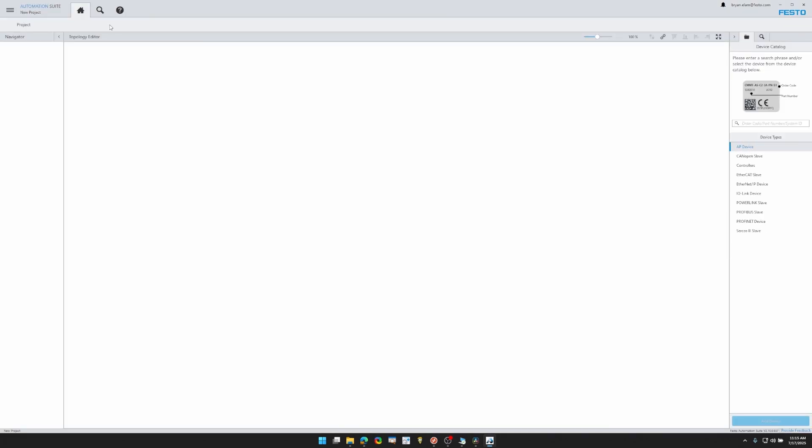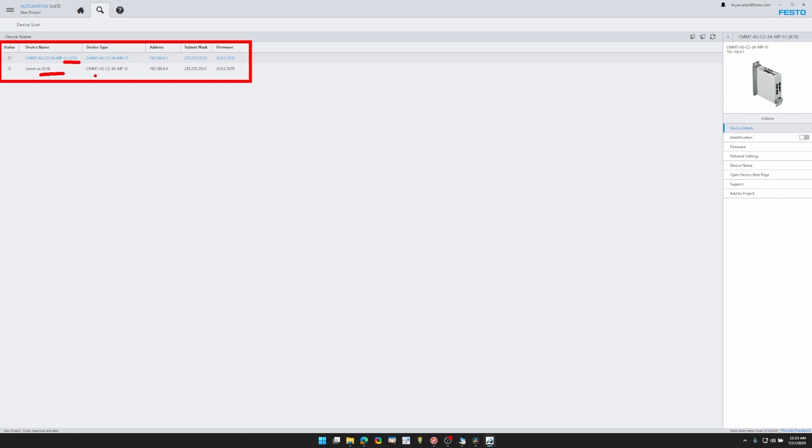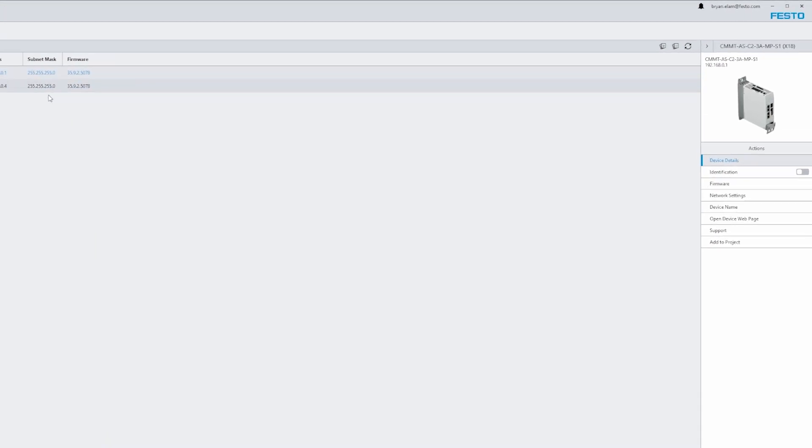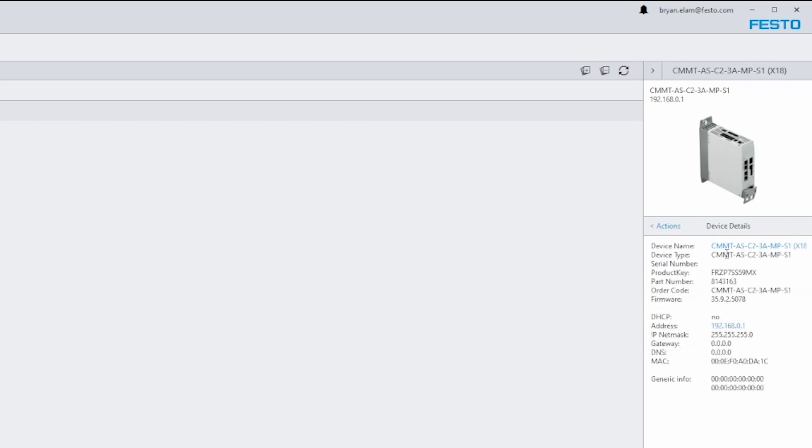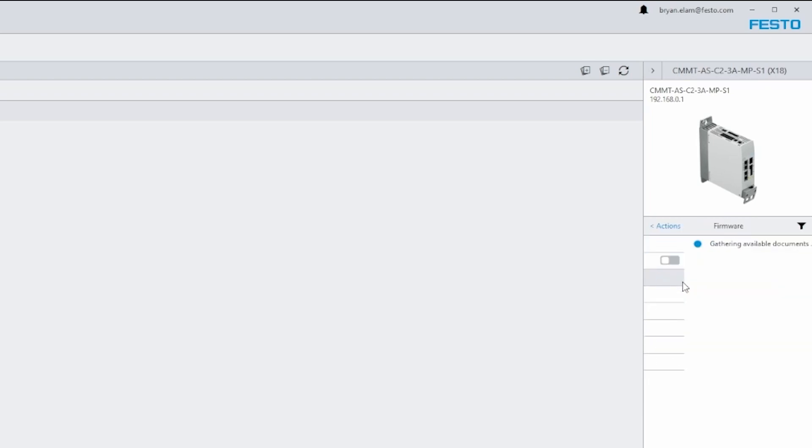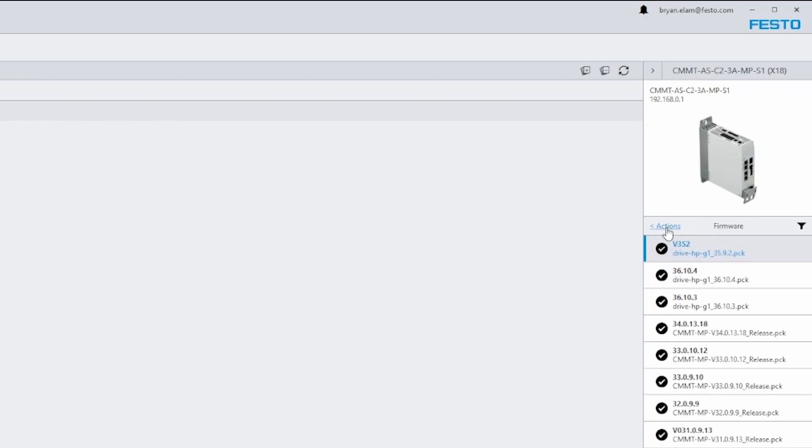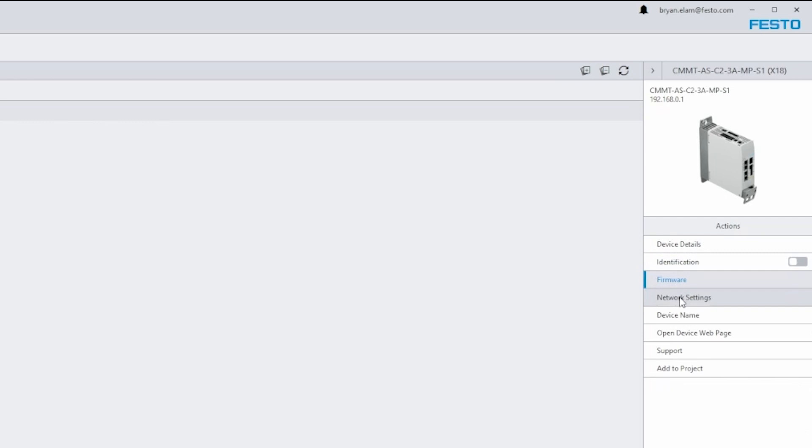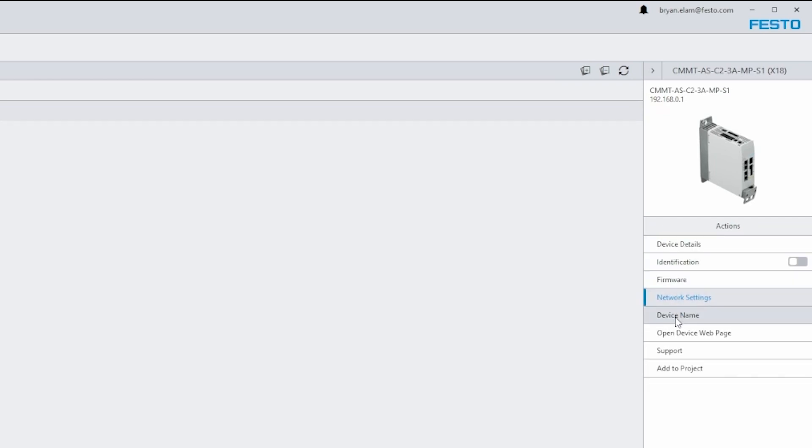Now we're going to go into a new project. We're going to go to this eyeglass for the scan. And here are the X18 and X19 ports. So the X18 port is for setting parameters for the drive. The X19 port is for field bus communications protocol. On the right you can see device details. So there's the name, the firmware version, the IP address, some good details there. Another thing is you can look at the firmware here if you needed to update it.